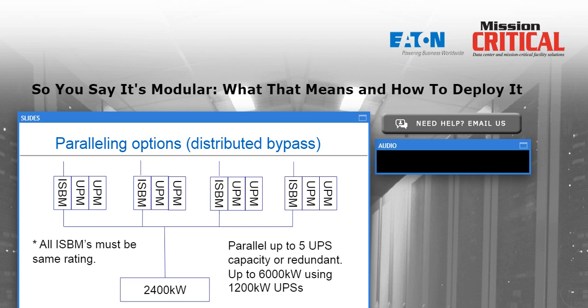So that means the failure of any one part, fuse, circuit board, semiconductor, fan, capacitor, will result in that individual power module disconnecting itself instantly from the others, and the fact that the UPS system is at that point not overloaded means that it will remain online with protected power and full battery backup until a service engineer arrives on site to effect the repair. So while there are more parts, there is the inherent redundancy which is typically used in a modular scalable system that, as a result, gives you better reliability over the life of the UPS.